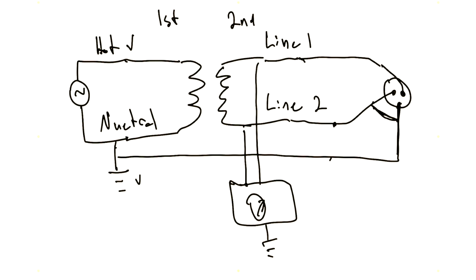Now, if a person over here were to come and touch line 1 or something at the potential of line 1, such as a medical device that has a broken wire or some broken device or something of that nature that allows them to be at the same potential as line 1, well, now they are touching line 1. Line 2 has already dropped down to the potential of the ground. So now there is a path from line 1 through the person, through the ground, so you can complete the circuit. Okay, and so this is a two-fault condition. The person would receive shock, and, you know, obviously the line isolation monitor would have gone off before this.